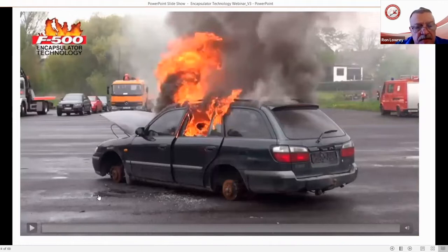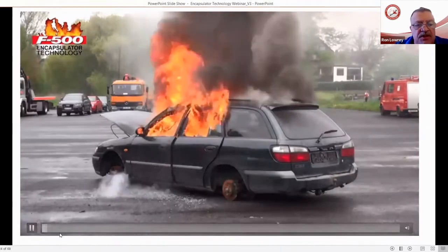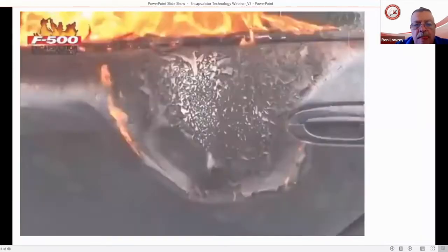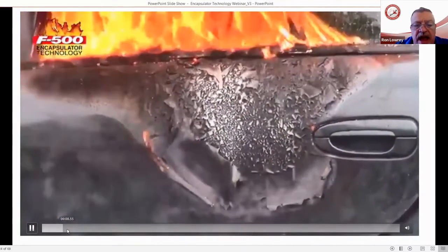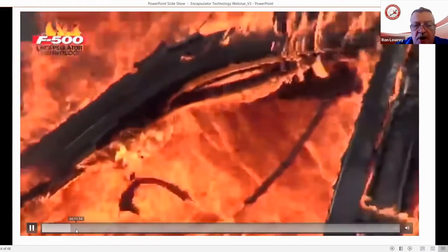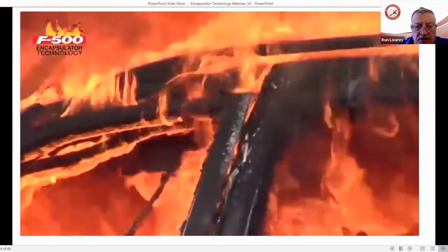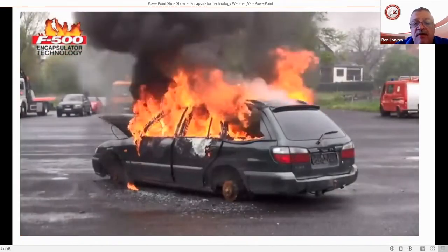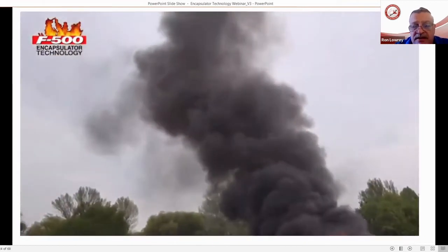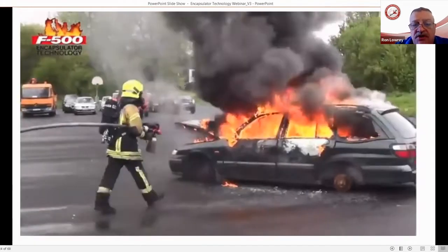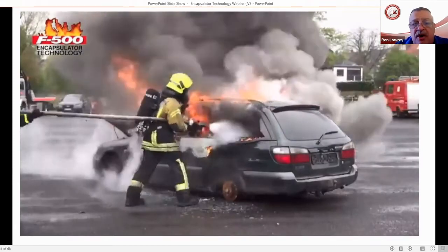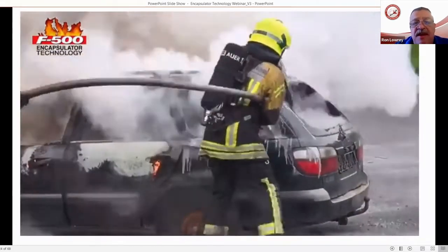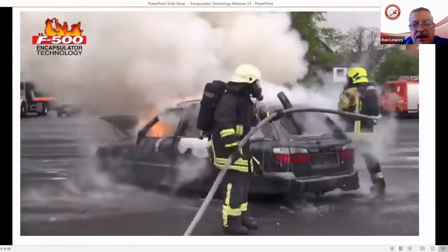This isn't the same video we saw earlier with the thermal imaging, but again, another fire. This is from our distributors over in Europe. Again, we're going to be using that 20 gallon per minute nozzle, so a very low flow nozzle. As you'll see, great fire suppression, very little runoff, very little environmental impact. Same way, just like we saw with the tires. Watch that heavy black smoke. As soon as they start applying on the fire, how rapidly that heavy black toxic soot-laden smoke disappears.